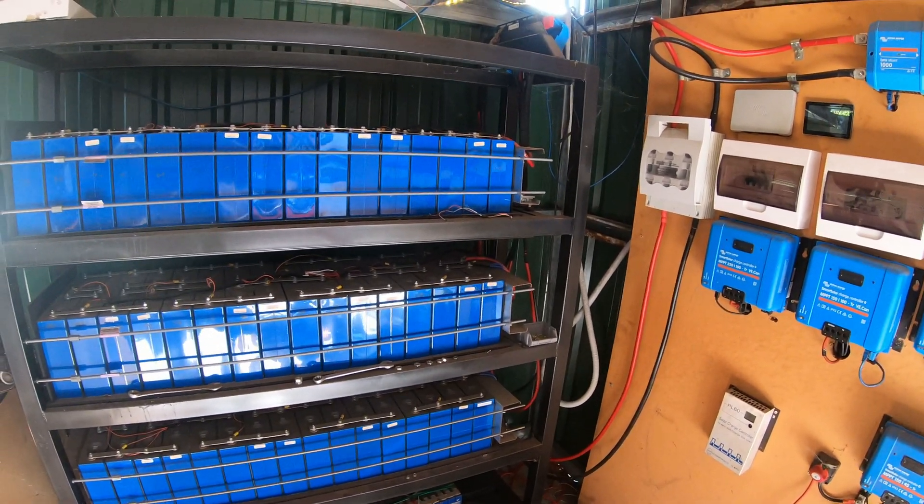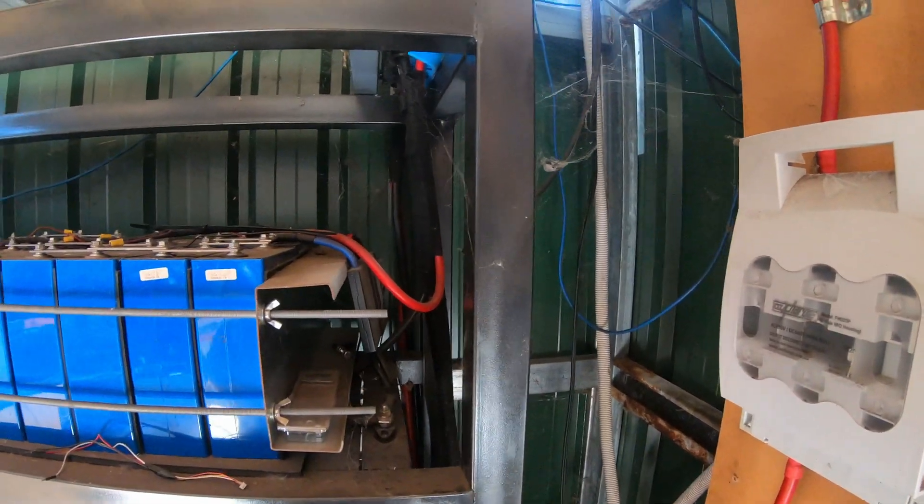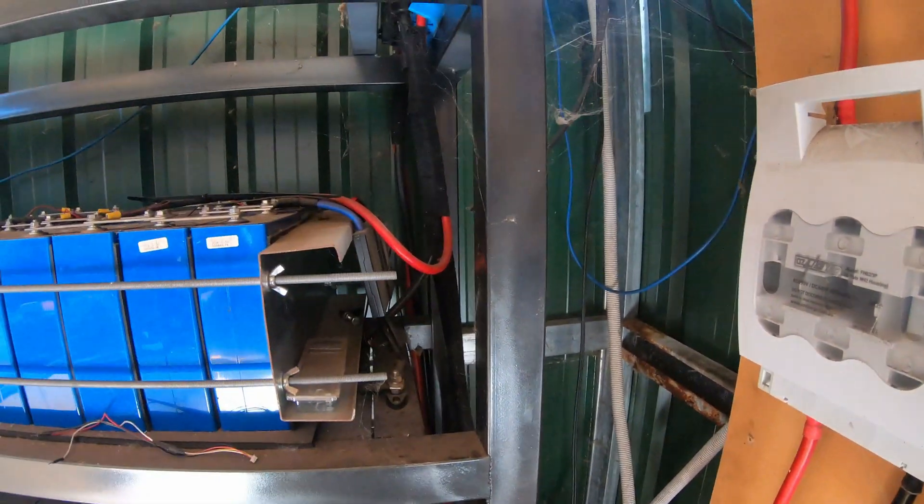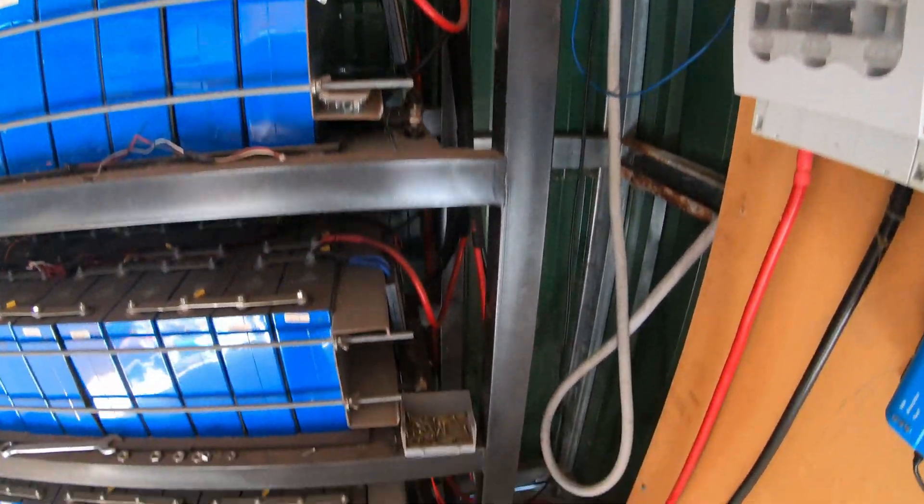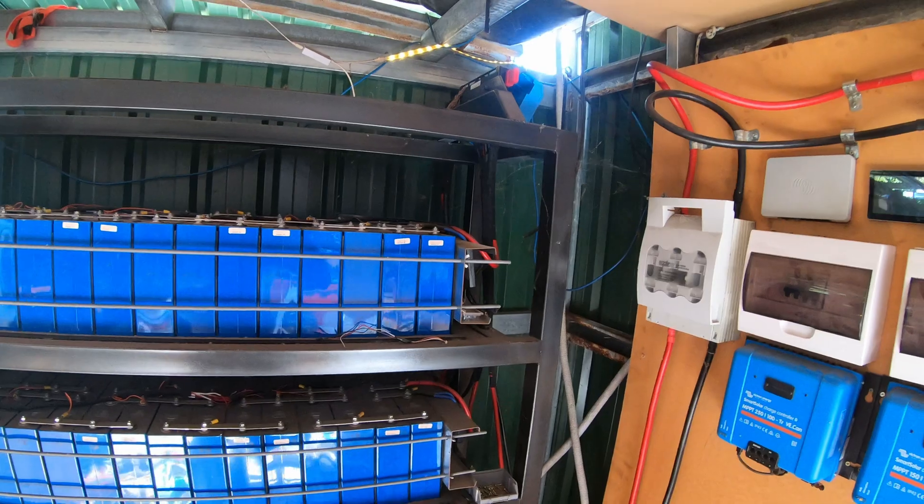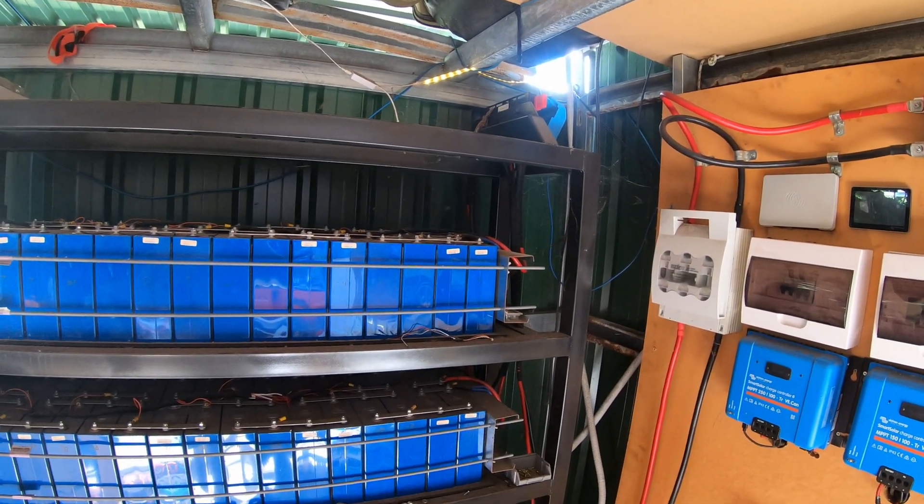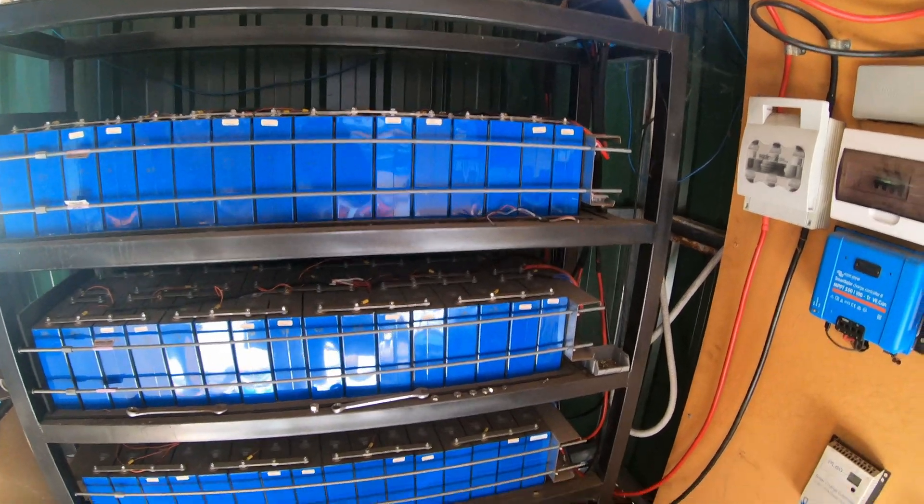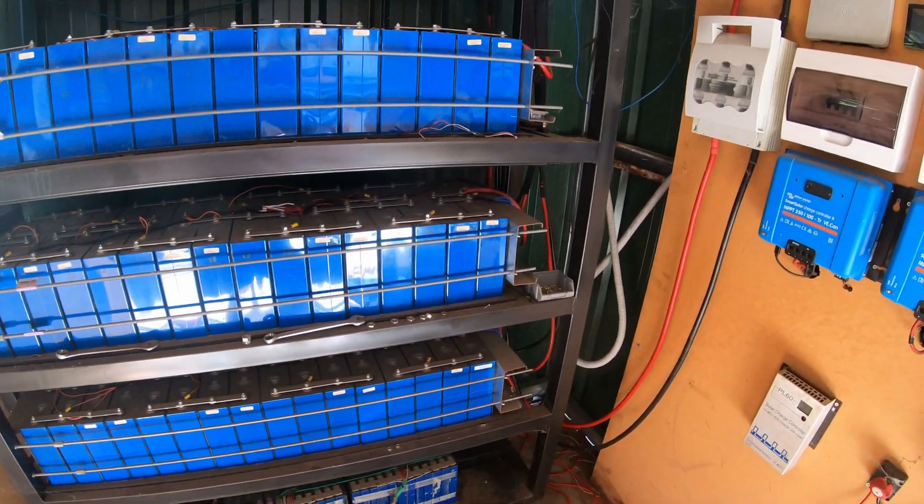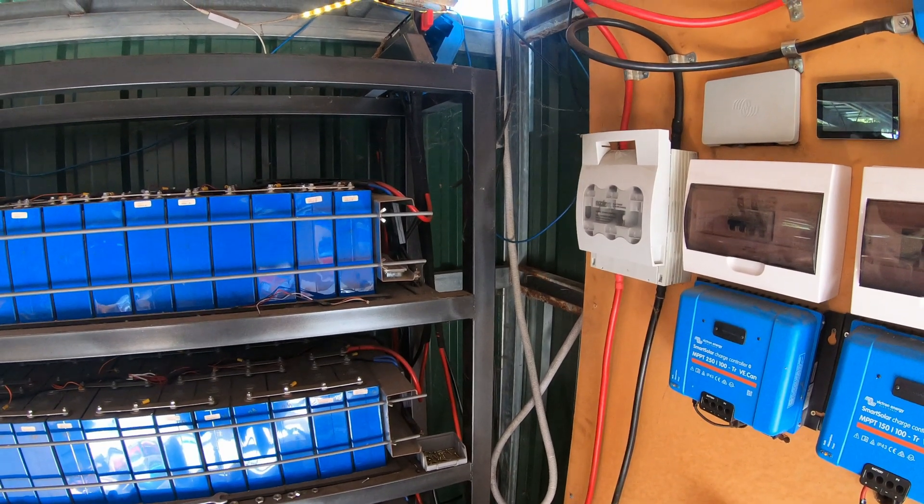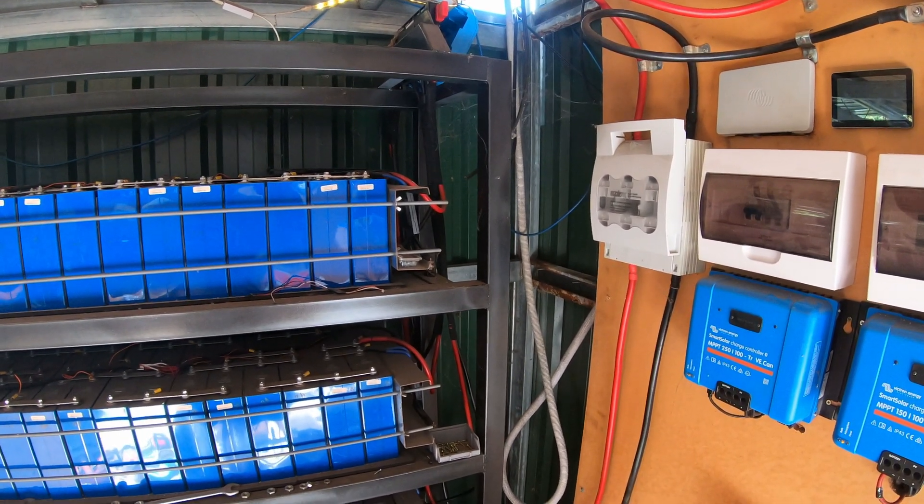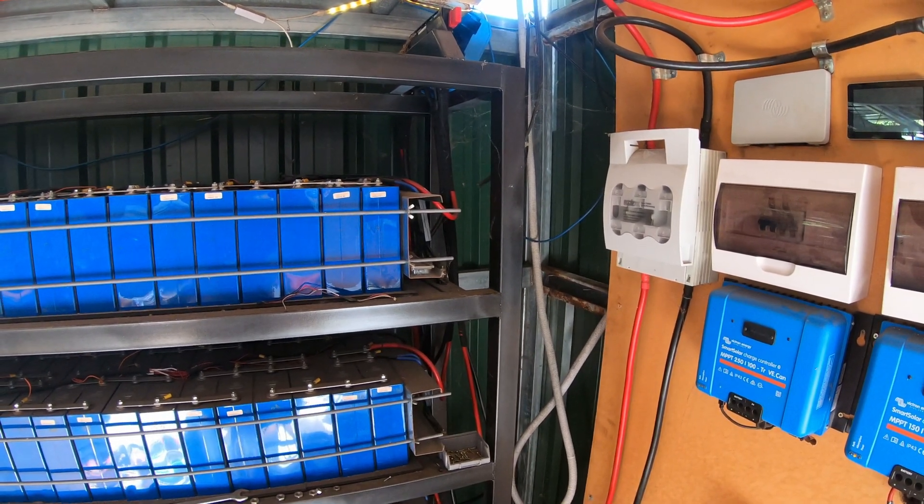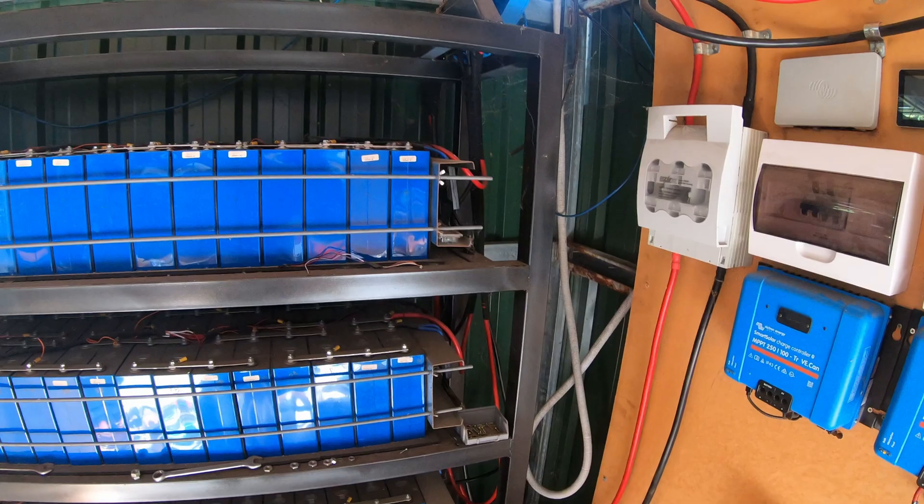For the guys with constructive criticism, we really appreciate it. You're 100% correct - the cables aren't exactly the same length. We added a couple hundred millimeters to get them roughly the same, but they're not exactly the same and that's not ideal. One of the guys mentioned they use 400 millimeter square copper bus bars and we shouldn't be seeing a huge difference on the cable. So today's video is going to be about that - we always blame the cable length, but if it's not the cable length it could potentially be something else.